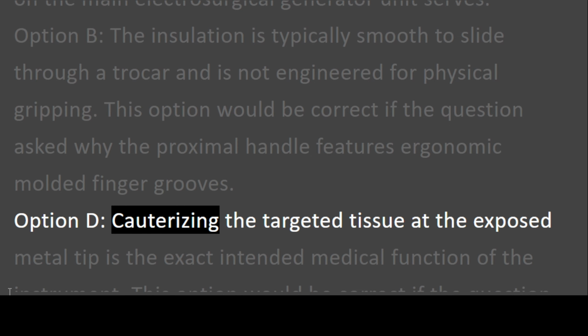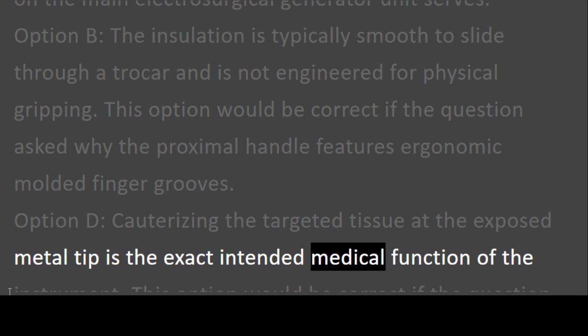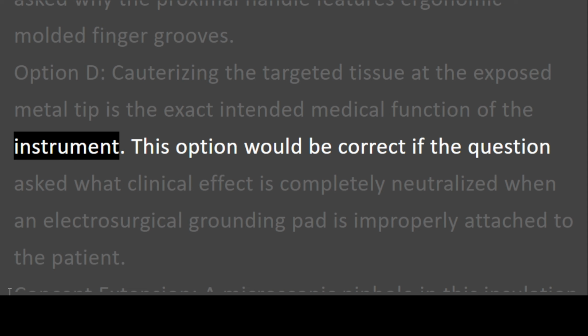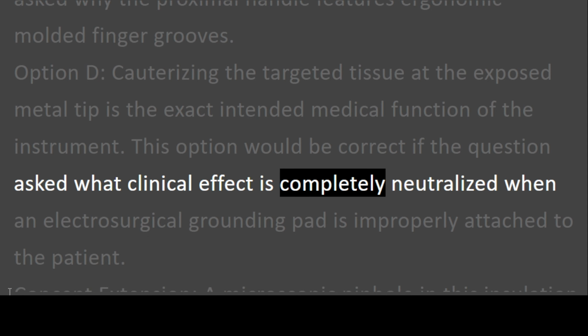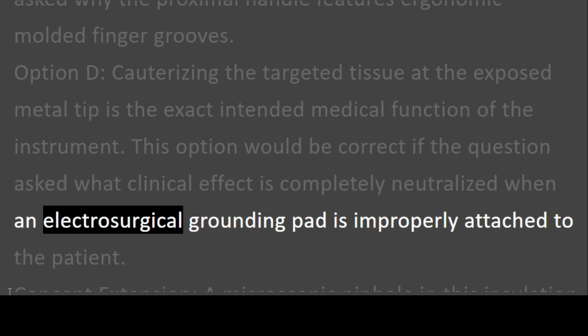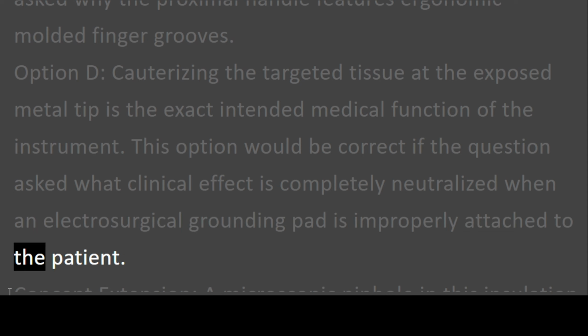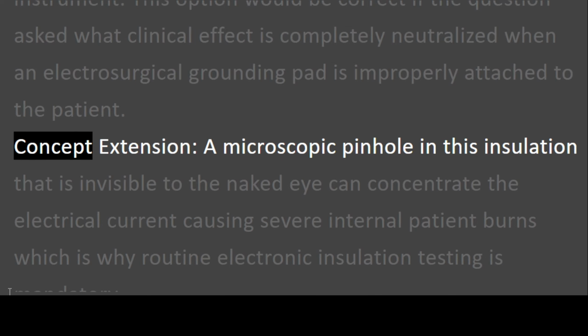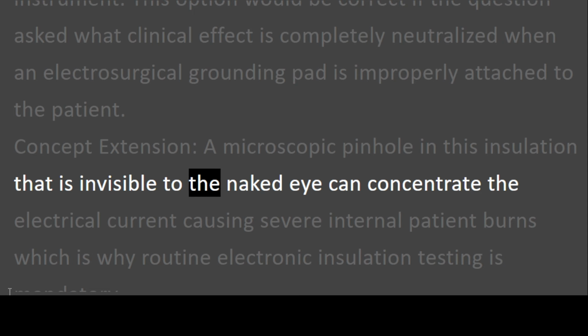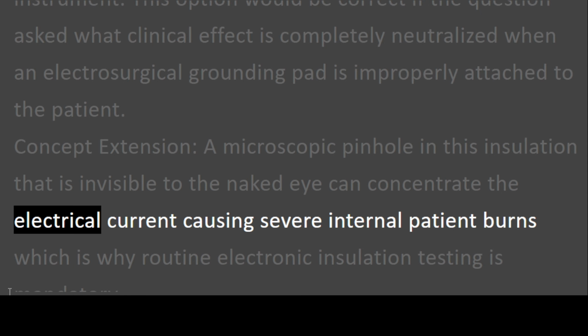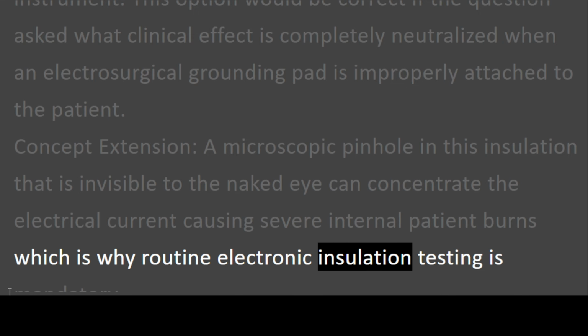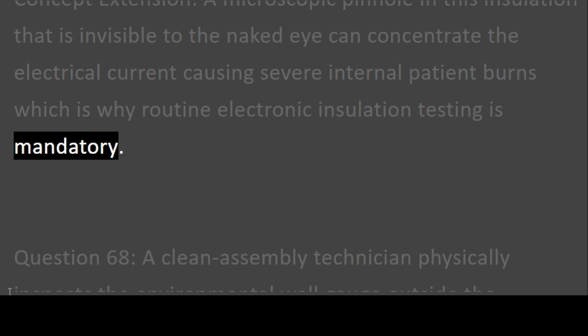Option D. Cauterizing the targeted tissue at the exposed metal tip is the exact intended medical function of the instrument. This option would be correct if the question asked what clinical effect is completely neutralized when an electrosurgical grounding pad is improperly attached to the patient. Concept extension. A microscopic pinhole in this insulation that is invisible to the naked eye can concentrate the electrical current, causing severe internal patient burns, which is why routine electronic insulation testing is mandatory.